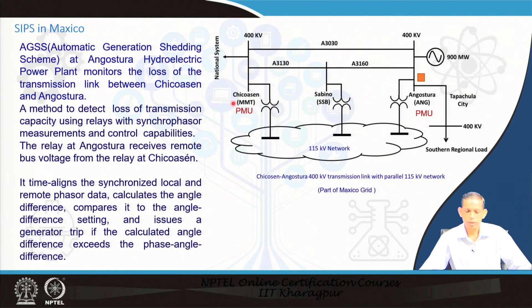Note, when both 400 kV lines are there, the corresponding angle is in a limit in general. When one line is out, the angle between this side and that side goes to a higher value, and when both lines are out, the angle becomes further higher. So, that is being noticed. In this automatic generator shedding scheme, the hydro plant gives 900 megawatt or so. So, a method to detect loss of transmission capacity is this angle measurement between these two stations.